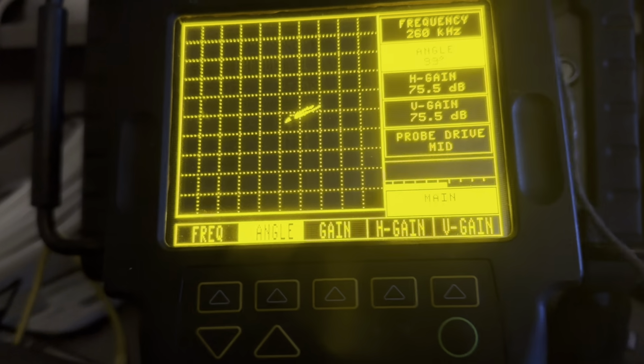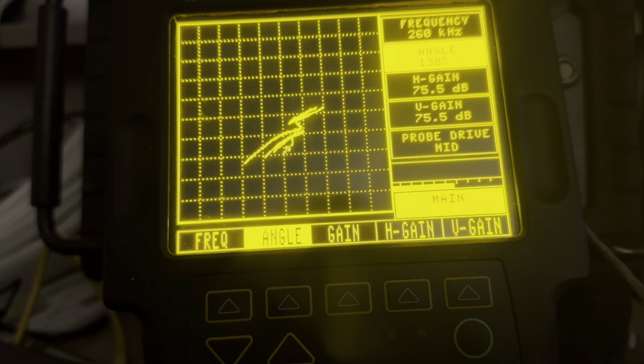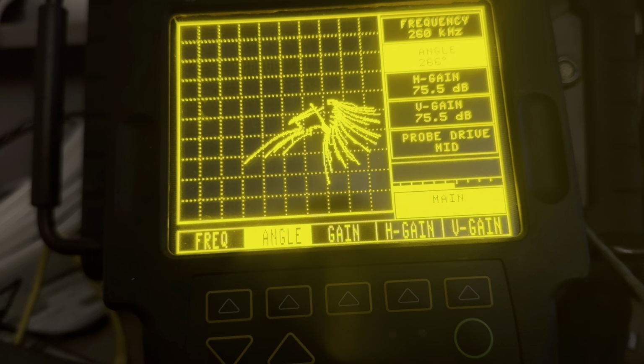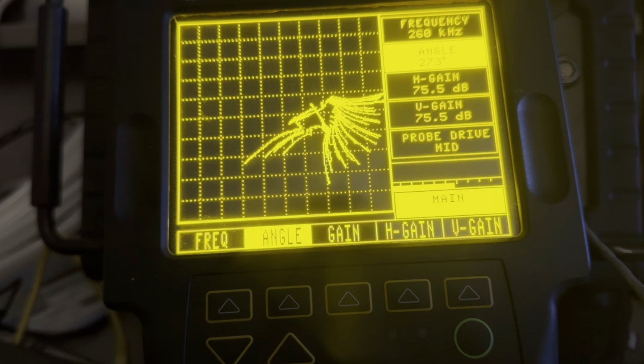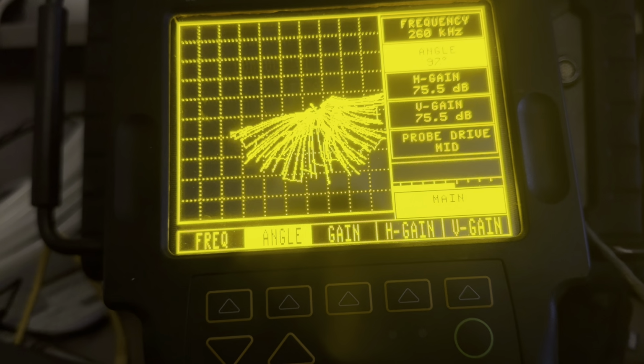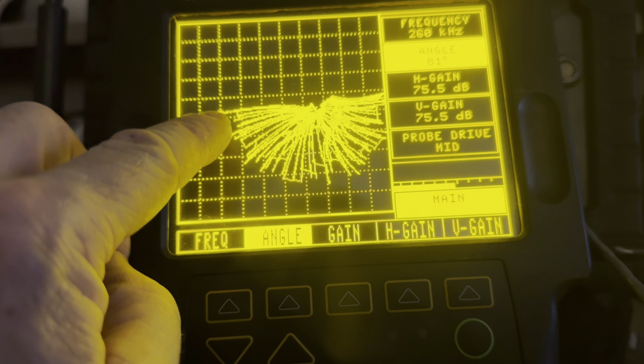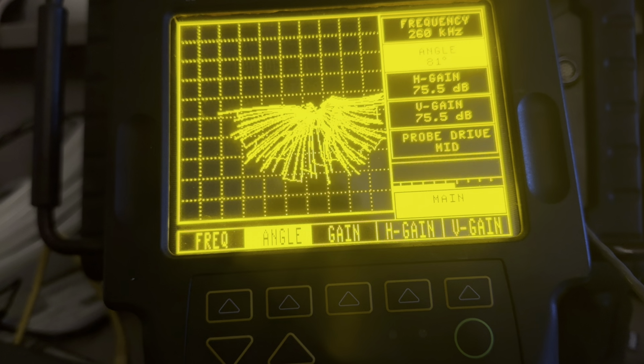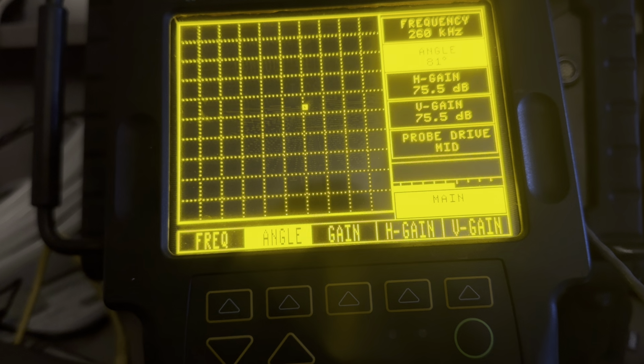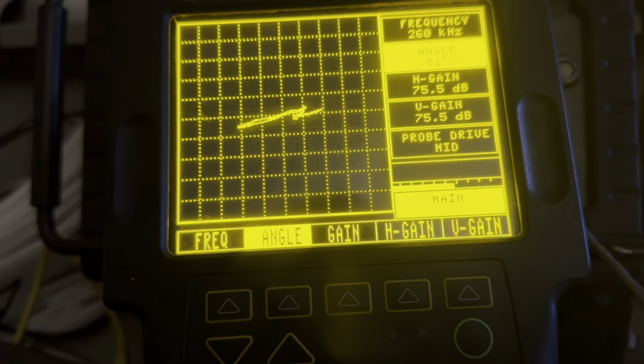Ooh, okay, so now I got that's my liftoff line. And again, with the surface probes, you normally have loaded to the right. That means I've got that upside down. So let's crank this back around, all the way around 180. You ever hear people say I did a 180? It means they did the opposite. So that's the unloaded operating point, coil and air, and that's the loaded point. That's the operating point of my test material.